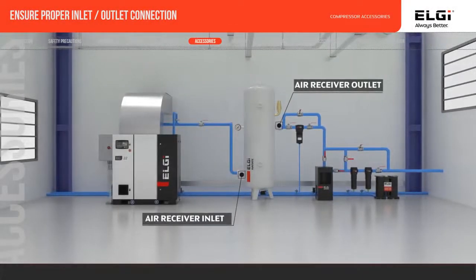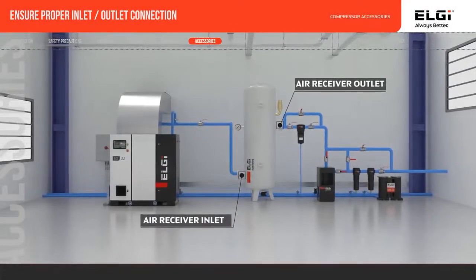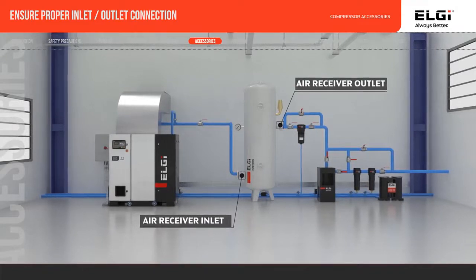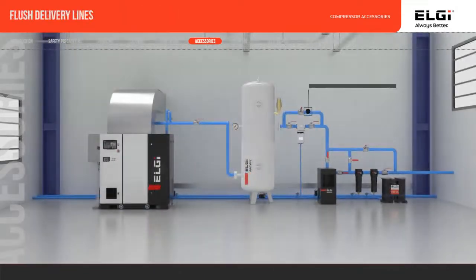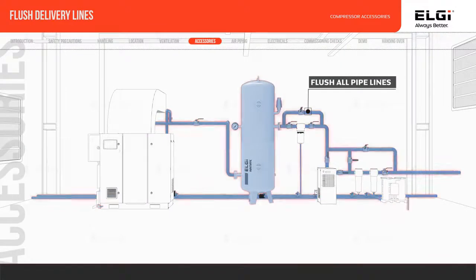Air inlet to the receiver should be at the bottom, and the outlet from the receiver should be on the top. The pipelines from compressor outlet to customer application point should be flushed before assembling all the downstream filters, such as pre-filter, a fine filter, and carbon filter.